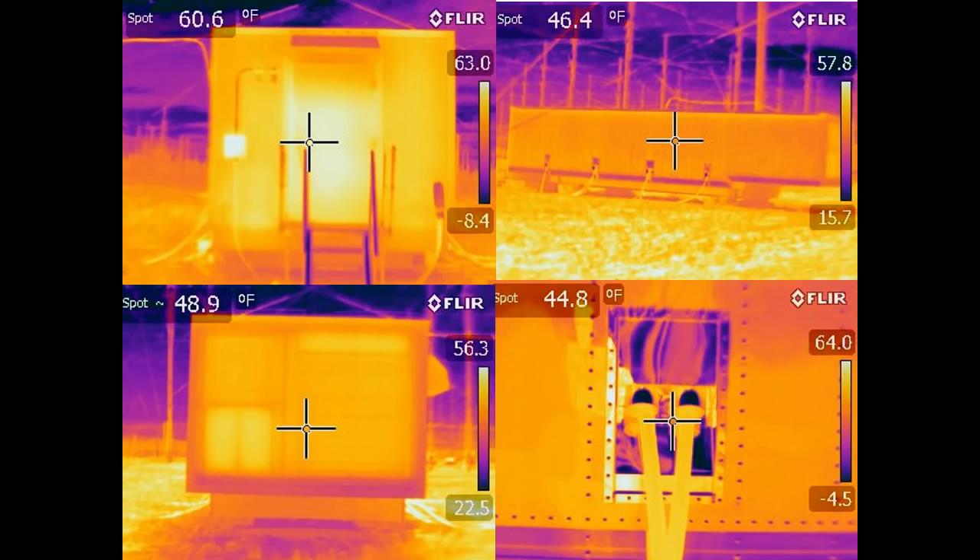The trailers shed a lot of heat. They're well insulated, but when HAARP is running there's an enormous amount of heat dissipated in those trailers through plenums. We've been looking at simple innovations to save money, like lowering the thermostat and using styrofoam to block some areas where heat escapes. The generators were also out of EPA compliance, and it was about a million and a half dollars to bring them into compliance. We worked with the EPA, the Alaska Department of Environmental Conservation, and the local power company, and came up with a scheme to provide 10% of whatever we generate free to a rural community — which we've done successfully by pumping power back into the Copper Valley Electric Authority.